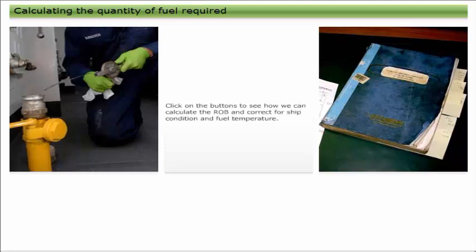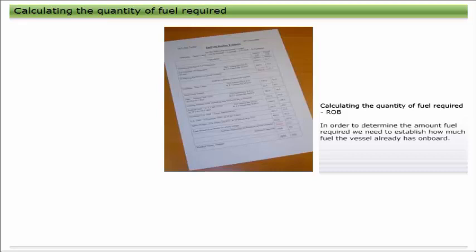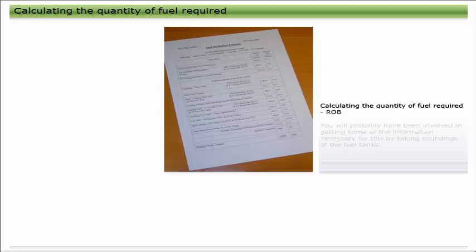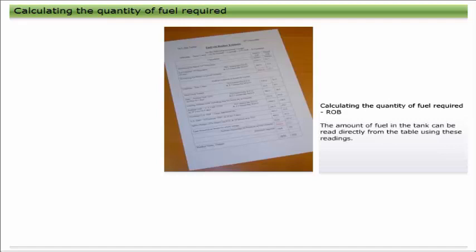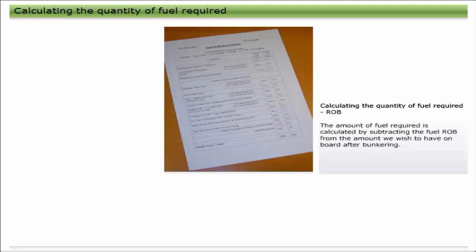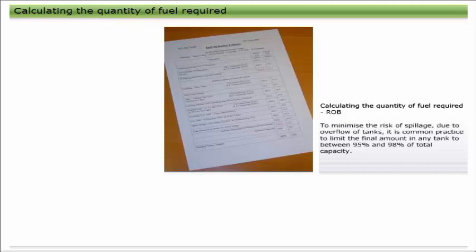In order to determine the amount of fuel required, we need to establish how much fuel the vessel already has on board — normally referred to as the fuel ROB (remaining on board). Soundings or ullages are taken of the tanks into which fuel will be loaded, and the amount of fuel in each tank is read from the capacity table. The amount of fuel required is calculated by subtracting the fuel ROB from the amount we wish to have on board after bunkering. To minimize the risk of spillage due to overflow of tanks, it is common practice to limit the final amount in any tank to between 95% and 98% of total capacity.